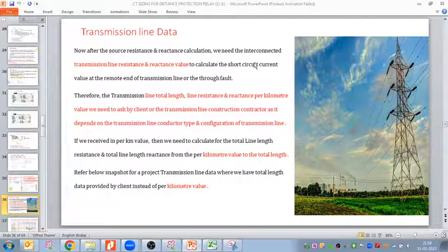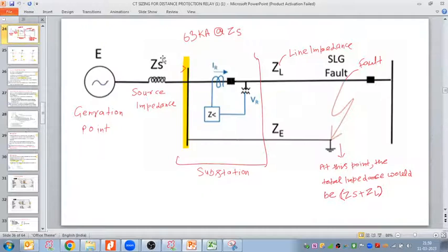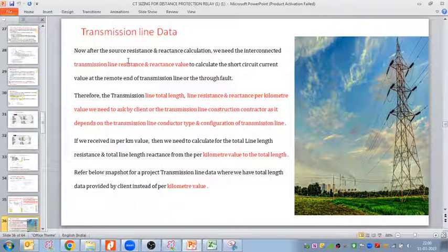Now after the source resistance and reactance, for the through fault current calculations, we are coming to the transmission line. We need the interconnected transmission line resistance and reactance value to calculate the short circuit current value at the remote end of the transmission line, that is, the through fault current. Therefore, the transmission line total length, resistance, and conductor reactance per kilometer, or for the entire length, we need to ask the client or the transmission line construction contractor, as it depends on the conductor type, configuration, and diameter they are using. So we need to ask them before starting the calculation.